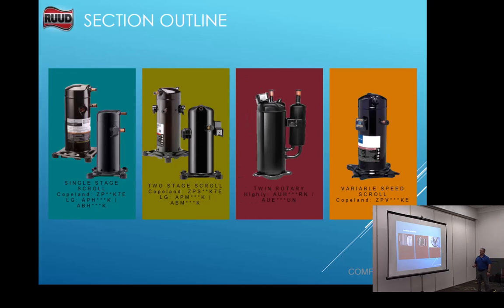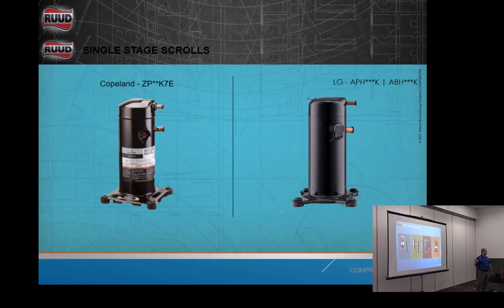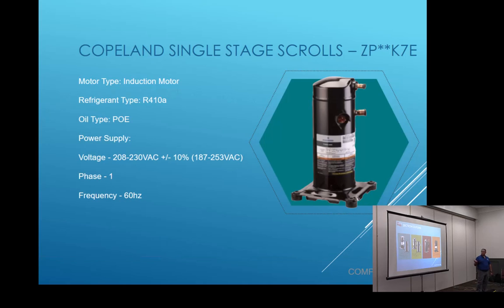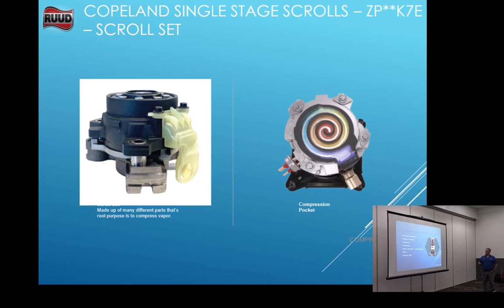We're going to get into a little bit of overview for our units and our compressors, what we've got going through, okay? We've got Copeland and LG compressors. We have our two-stage Copeland and LG. We're going to talk about our differences there. We have our high-efficiency twin rotary, which is for our 15 and 16 SEER systems. And then our variable speed scroll that we've had forever on our 17s and 20s, okay? Still a great compressor. I love it. Our regular compressor on both the Copeland and the LG is the same. POE oil, 208/230, single phase, 60 hertz compressor.